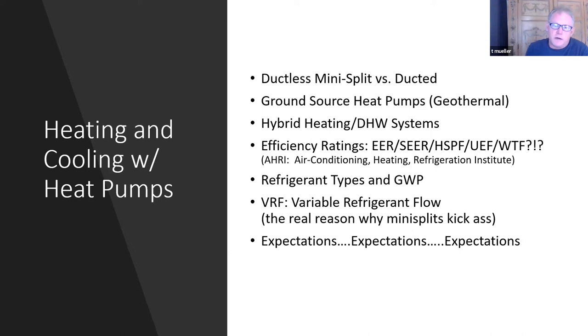It delivers air through the registers that's typically in the 90 degree range rather than the 120 degree range, and it runs for a longer time with slower velocity. If your heat pump system is designed properly, it should be on pretty much the entire day. It might change speeds, but it won't come on and off like a gas furnace system will.